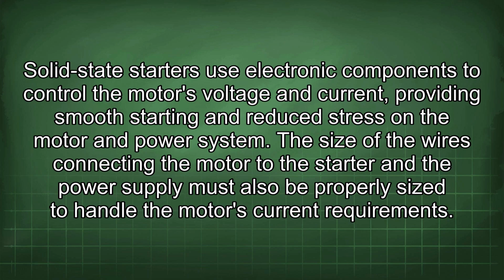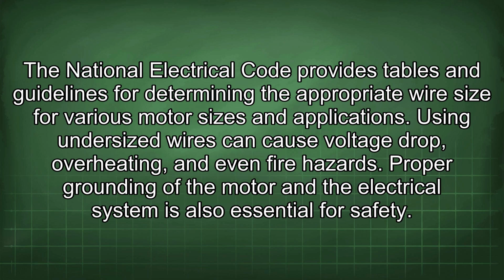The size of the wires connecting the motor to the starter and the power supply must also be properly sized to handle the motor's current requirements. The National Electrical Code provides tables and guidelines for determining the appropriate wire size for various motor sizes and applications. Using undersized wires can cause voltage drop, overheating, and even fire hazards.